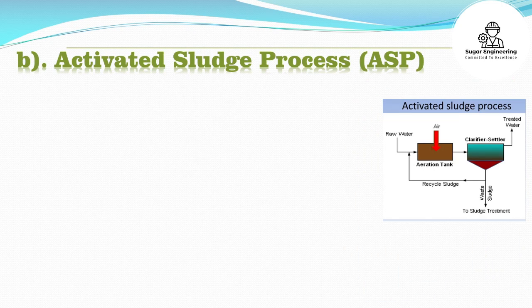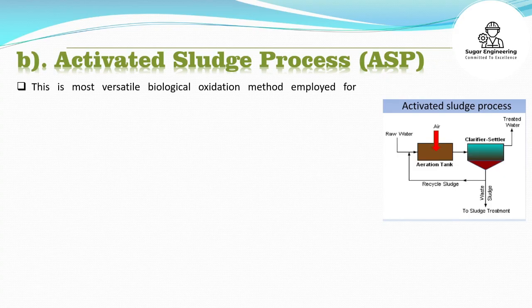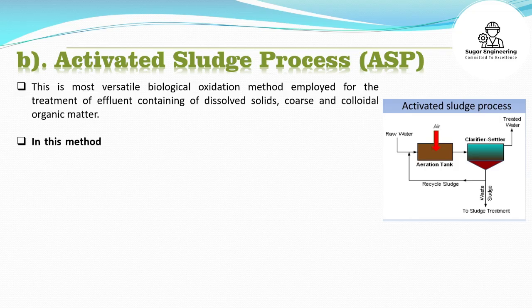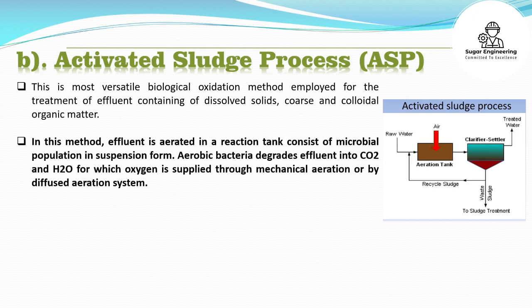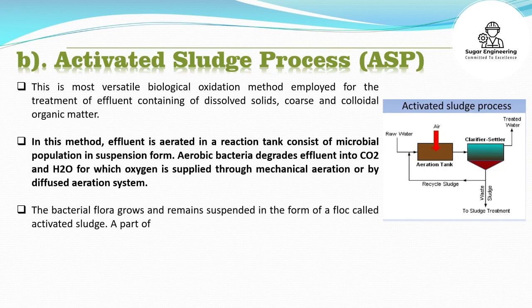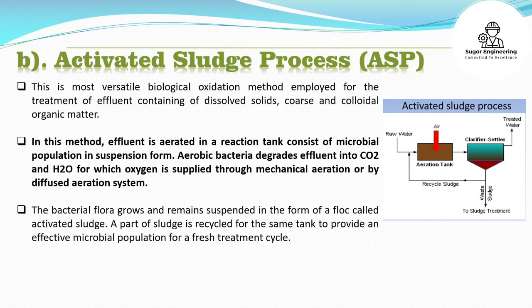Activated sludge process is the most versatile biological oxidation method employed for the treatment of effluent containing dissolved solids, coarse, and colloidal organic matter. In this method, effluent is aerated in a reaction tank consisting of microbial population in suspension form. Aerobic bacteria degrade effluent into CO2 and H2O, for which oxygen is supplied through mechanical aeration or by diffused aeration system. The bacterial flora grows and remains suspended in the form of a floc called activated sludge. A part of sludge is recycled to the same tank to provide an effective microbial population for a fresh treatment cycle.